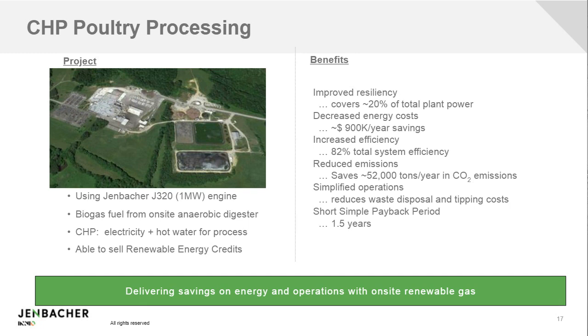This is an actual project that produces 1 megawatt per hour with a J320 engine. So more or less, they produce electricity and hot water for processes, and they get approximately $900,000 per year in savings. In summer, it's more, where they can even receive up to $150,000 per month. It has an 82% total system efficiency, and emissions reductions are 50,000 tons of CO2 per year. It is a very well designed and thought out project.